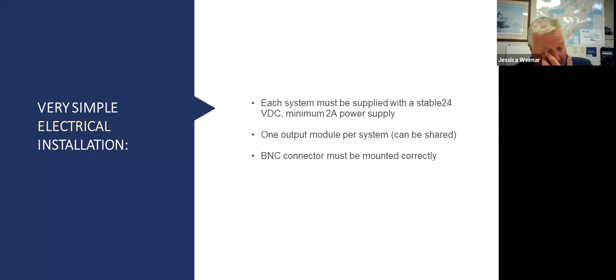So think about the other things to consider here, and we can move through this relatively quickly, but these systems run on 24-volt DC, and they require very little power. It's minimum a 2-amp power supply. We can provide a 110-volt converter in the enclosure. We do it routinely, so if you want to plug it into the wall, you can.